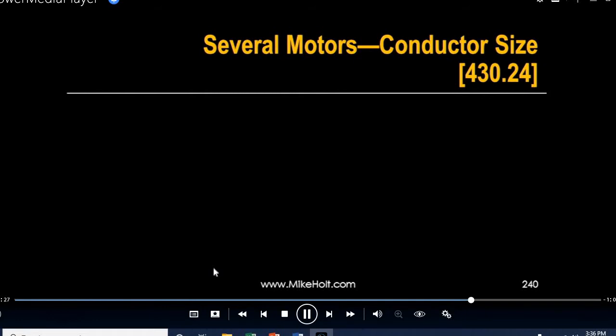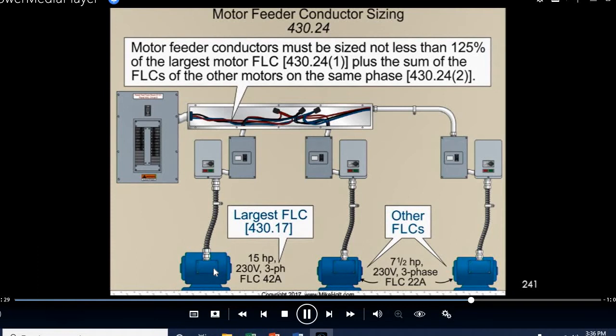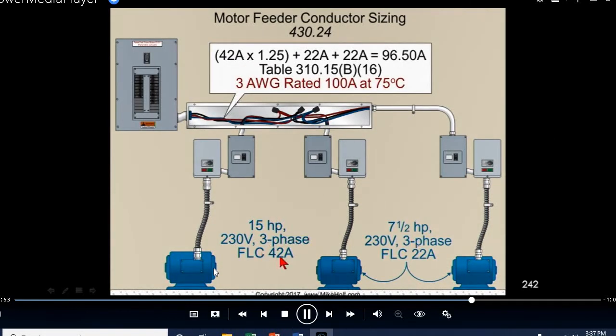Now, if you have several motors, and you're trying to size the wire for several motors, let's say one motor is 22 amps, one motor is 42 amps. The code says the feeder conductor, which is a conductor for several motors, must be sized not less than 125% of the largest, which would be 42 times 1.25, plus the sum of the other motors on the same phase. Well, then there's one other one, which is 22. And if I do the calculation, I would take the 42 times 1.25 plus the 22. Oh, this example is showing two motors. Okay, 2 motors. So 42 times 1.25 plus 22 plus 22 comes out to be 96.